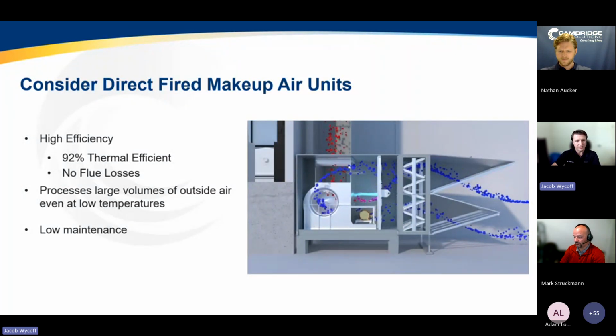We really see these in your high outside air applications for a few key reasons. Number one being that they're highly efficient. They're the most effective way to heat a space using natural gas. Because you have that combustion process directly in the airstream, you have no flue to lose any heat, and you're going to get that great 92% thermal efficiency out of the heater and 100% combustion efficiency.